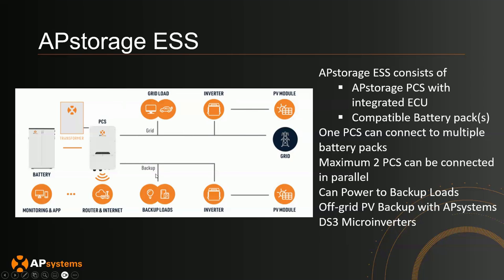We also have a backup section where you can put a sub-panel with your backup loads connected to it, and you can also put an inverter and PV modules in this section as well. The key difference is the top section works only when the grid exists — when the grid goes down, the top section will not function. But anything connected to the backup bottom section will remain functional: the PV, the inverter, and the backup loads will all function in off-grid. Note that the backup off-grid PV section can only use APSystems DS3 microinverters, but for the grid-only section, any inverter can be used since it's an AC coupled solution.